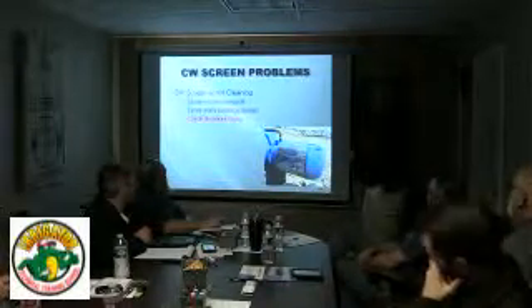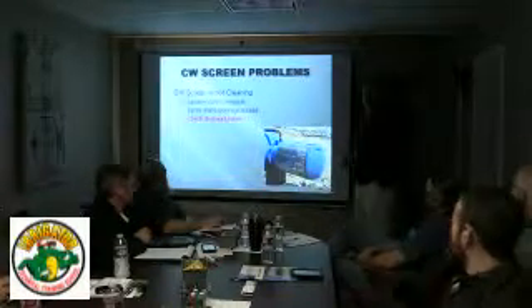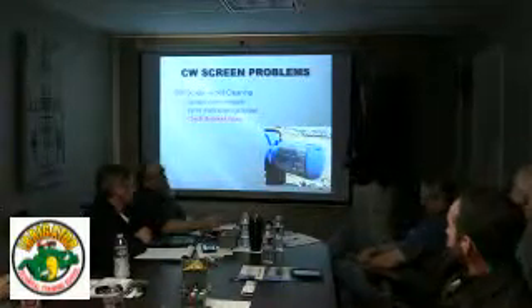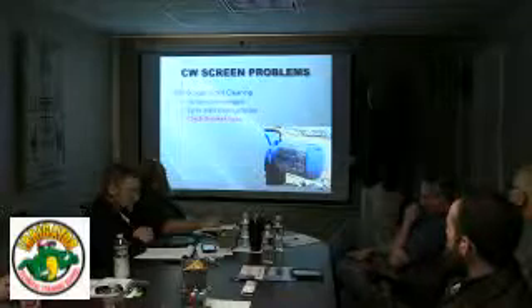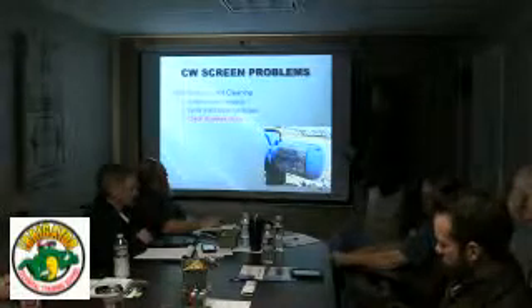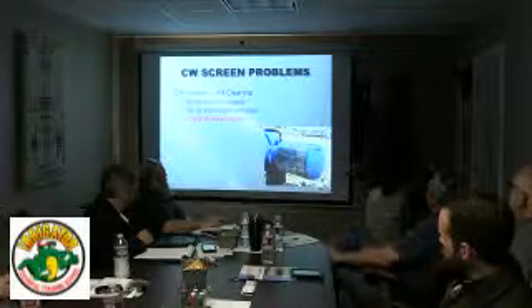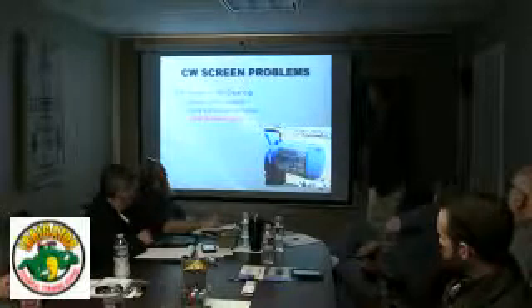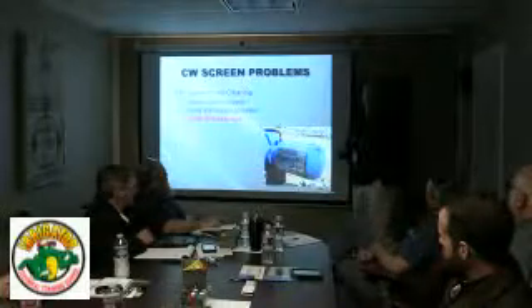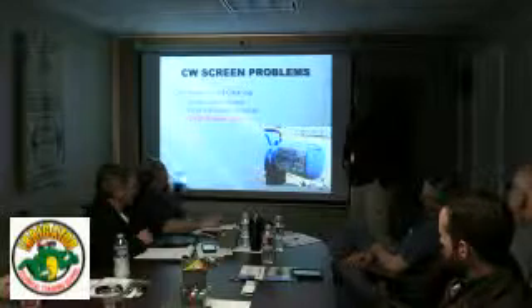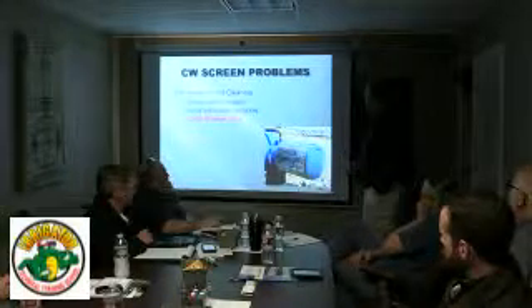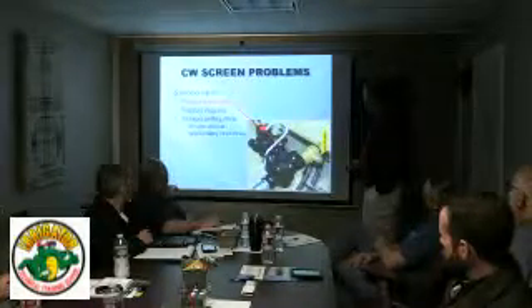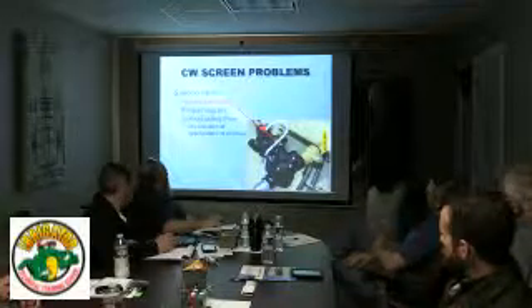Solenoid valve, again, that's that 1-inch Rainbird valve that's 24-volt AC on the pump station. Make sure that it's operating. If it's not opening or there's a problem with that, you're not going to get water out here to these wands. And in some places, it doesn't take long for this basket to start to build up with debris and restrict the flow going in there.